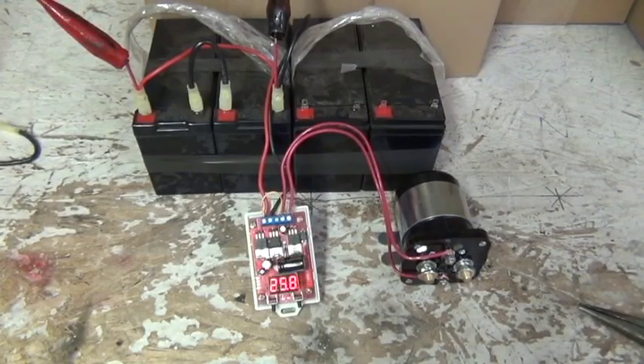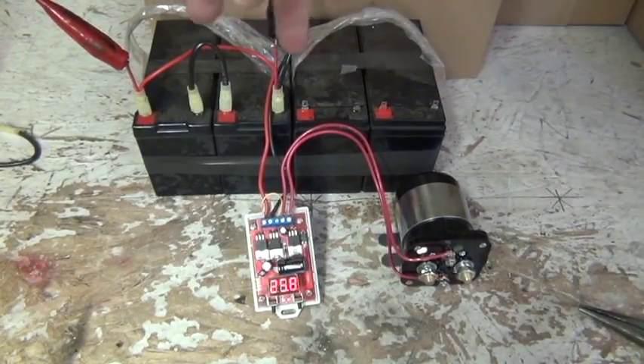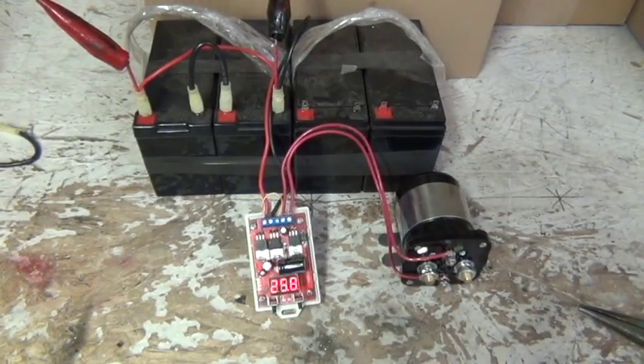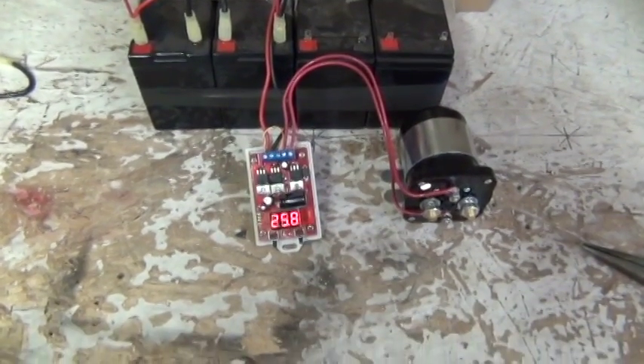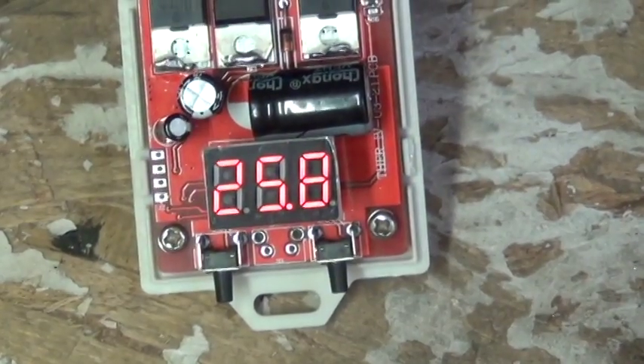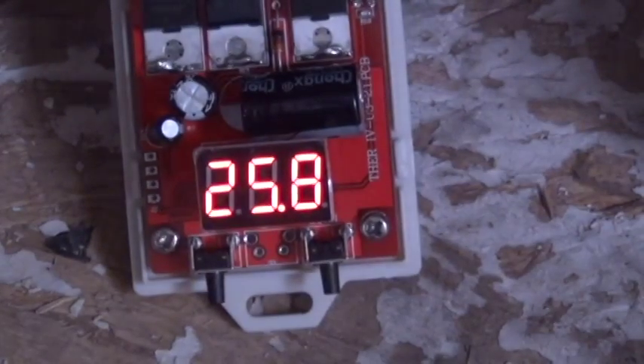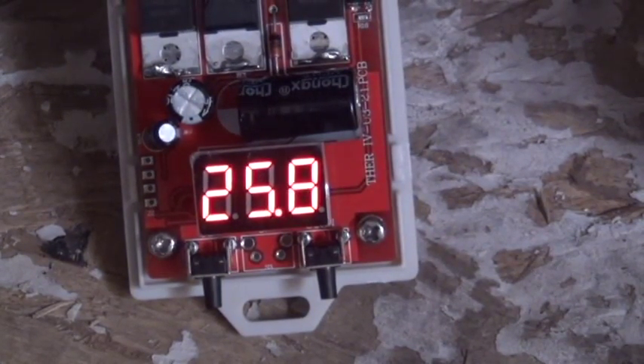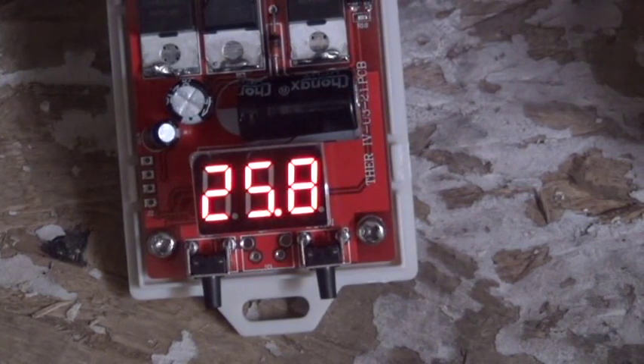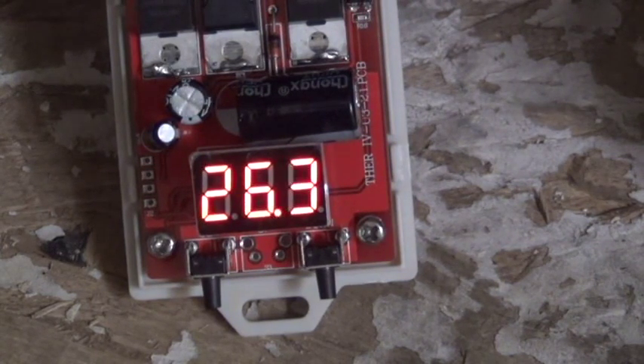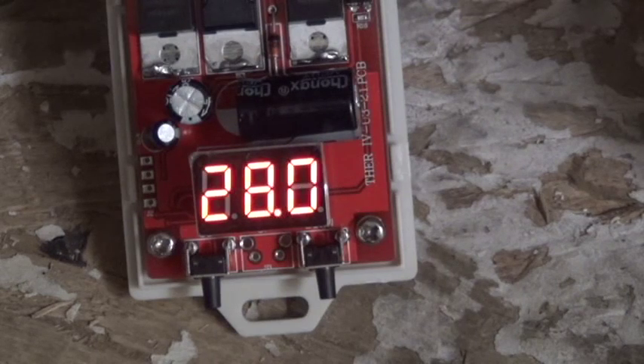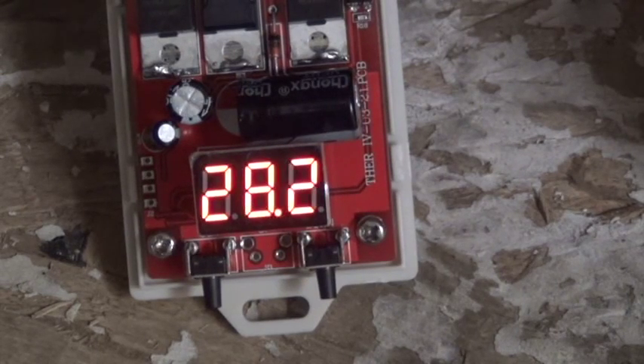This is the 24-volt setup. We change this to 24-volt. We've got two 12-volt batteries. 24-volt relay. Let's zoom in on the power meter and turn off the lights and watch it work. I'm going to be turning the Variac. We're going to be looking for 28.8 or higher. There it goes.